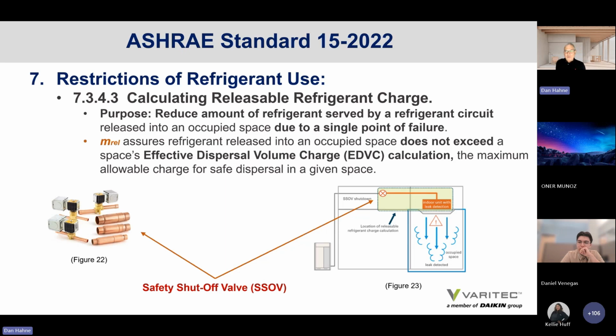But let's look at calculation of refrigerant for an occupied space. Calculating releasable refrigerant charge provides the amount of refrigerant served by a refrigerant circuit released into an occupied space due to a single point of failure. There may be multiple points served by a common condenser that can be isolated using safety shutoff valves in each independent circuit, which will lower the amount of refrigerant serving each space to allow them to more closely meet their RCL requirements per Standard 34. So M sub REL, the releasable refrigerant charge, assures that the refrigerant released into an occupied space does not exceed a space's effective dispersal volume charge calculation.